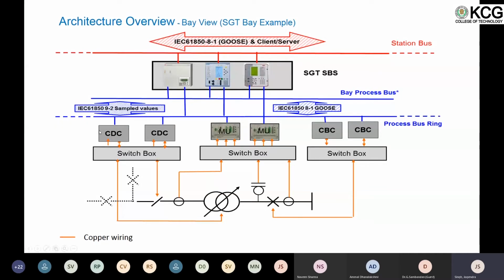So all these things together come here as a process bus, where you have relays connected, where you have the control system connected to the process bus. What is the process bus? The process bus is a communication network merging all digital and analog signals coming here through fiber optics and going towards the station process controller via the station bus.